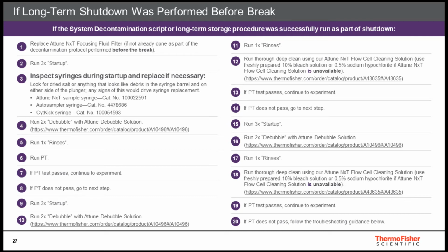During the startup process, please check the syringe on the Attune NxT and the Autosampler or CytKick for signs of leaks. Run the performance test. If the performance test passes, continue on with your experiments. If the performance test does not pass, go through the 3-2-1 steps to prime the lines, followed by deep clean using the Attune NxT Flow Cell Cleaning solution. Repeat the performance test. If it still continues to not pass, use the troubleshooting guide for guidance. If that does not help, please contact Thermo Fisher Scientific Support with the serial number to open up a service call.